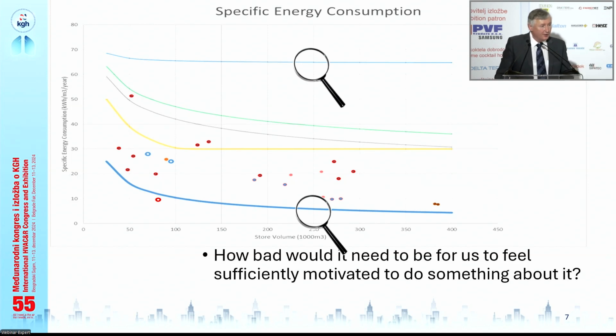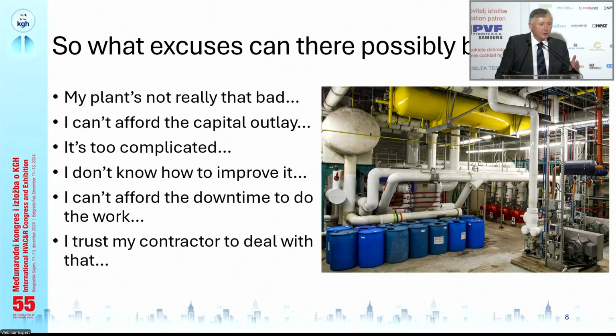That's how shocking this graph is, and you really need to be paying more attention to this, because that average is not acceptable. So what excuses could there possibly be for accepting an average that's as high as that? Some people might say, well, my plant's not really that bad. The room is cold enough. The product isn't being spoiled. That's my measure of success, is the room cold enough? That's not good enough. I can't afford the capital outlay to improve the plant. That's another excuse that you might hear.